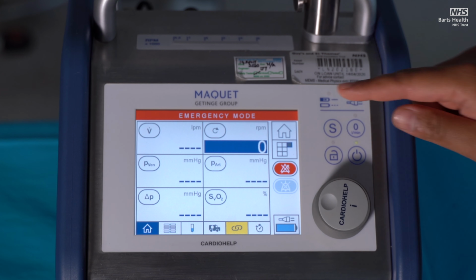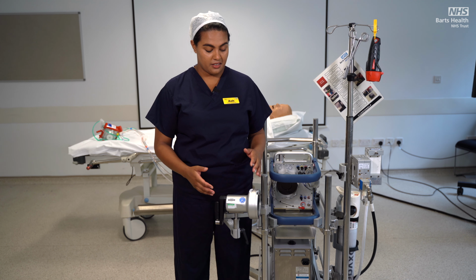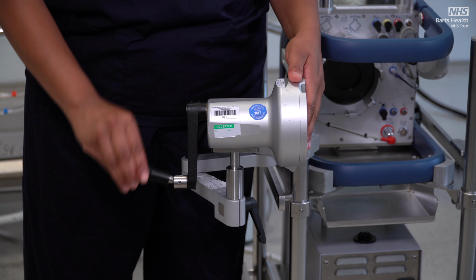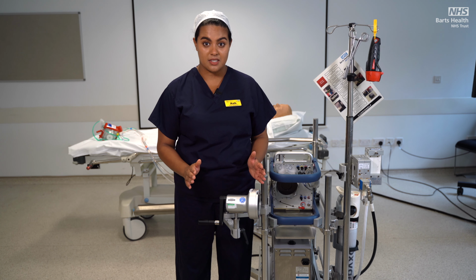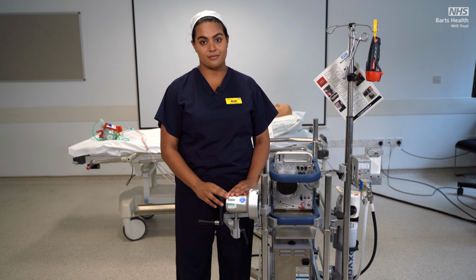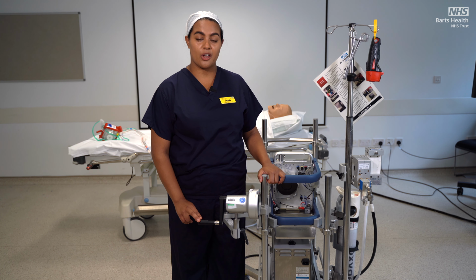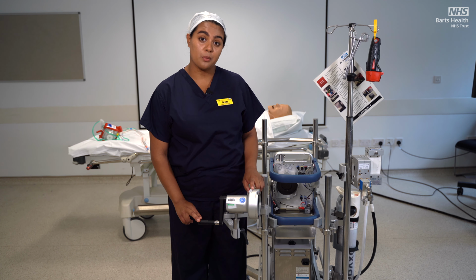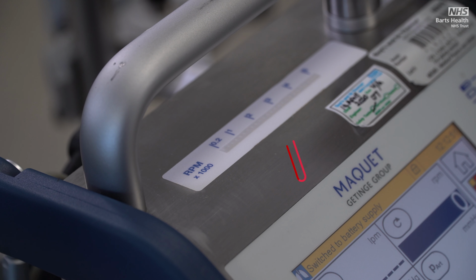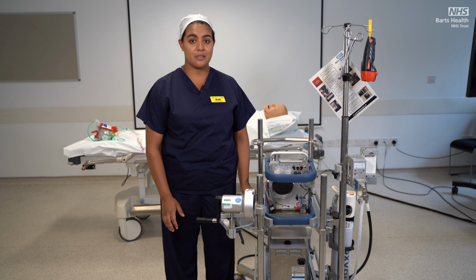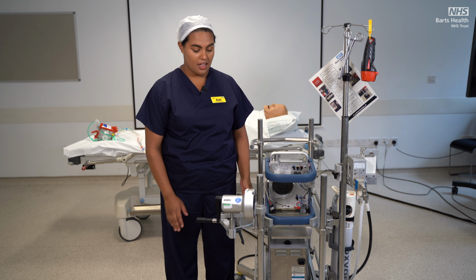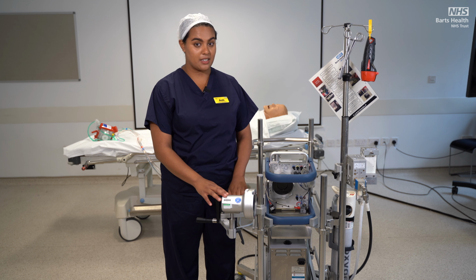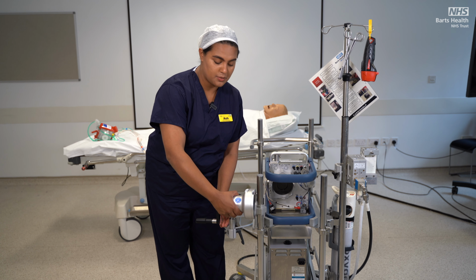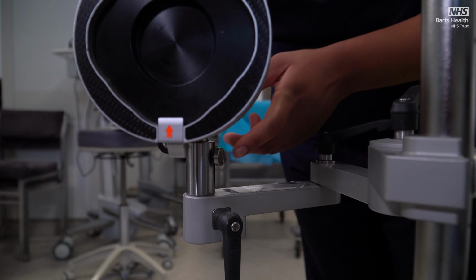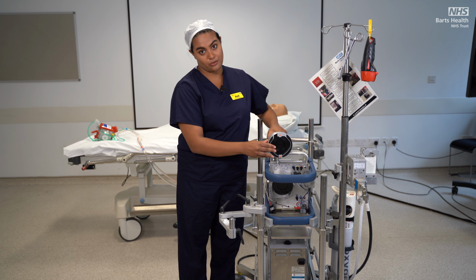The status bar of the touchscreen will continually display emergency mode in red, but no other alarm or message will be heard or seen. In the event of a motor failure, the emergency drive unit and the hand crank can be used to generate RPMs to maintain patient flows. The flows generated by the hand crank can only be seen on the touchscreen. The RPMs, however, can be seen at the top of the drive unit as well as on top of the console. Whilst the ECMO is stationary and by the bedside, the hand crank is mounted onto its own bracket. However, during ambulance transport, the hand crank will be mounted directly onto the console, like this.